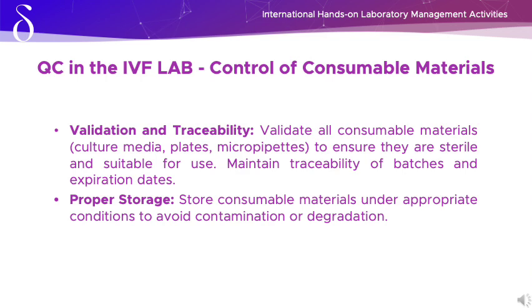Also, all the consumable materials must be controlled, periodically checked before their use, and before they are introduced in the lab for the first time. We have to validate the intended use, understand if all this material is valid for our procedures. We need to maintain traceability of batches and expiration dates, and check periodically that all the material is not expired. If it is expired, it must be stored apart in a designated area, with a label stating that the material is not conforming, in order to avoid misuse.